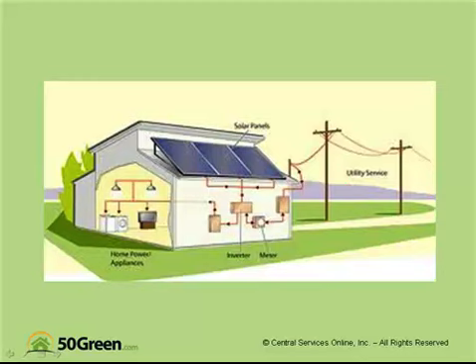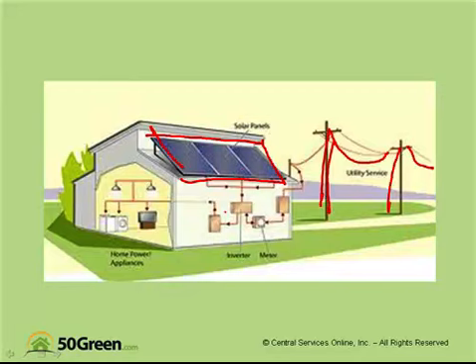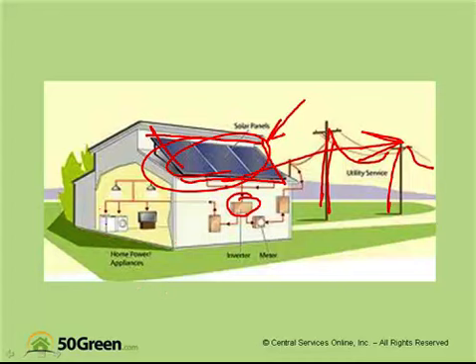So what is a grid-tie system? A grid-tie system is simply solar panels mounted on a roof that connect to the existing power system. The sun hits these panels and creates DC electricity, which goes to an inverter box, converts DC to AC — which is what we use — and actually makes your meter spin backwards when you're using less electricity than you're producing. During the day, solar panels make the most electricity, which is also when peak demands are for electric companies. At night when you come home and turn your lights and appliances on, you draw back from the grid and pay the net amount — the electricity you use over and above what you produce. If you produce more than you use, in some cases you actually get paid for that.